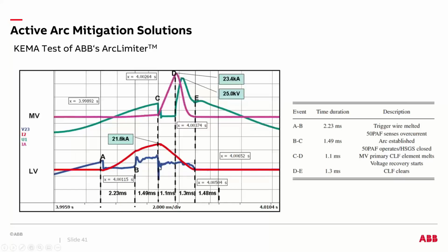Because the voltage has completely gone down to zero, right? So this point is where the voltage on the system is limited to zero. And in about 1.1 milliseconds, the primary current limiting fuse starts melting and it clears in about another 1.3 milliseconds. So in a total of about 3.8, 3.9 milliseconds, about 4 milliseconds from the time the arc flash has been detected, we have completely cleared the arcing fault, as well as cleared it by the upstream fuse that clears in about 1.3 milliseconds, right? In total, about 6 milliseconds from the time an arc flash has initiated in your equipment, you have completely eliminated and isolated any kind of fault in your system.